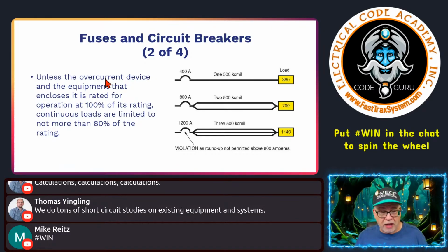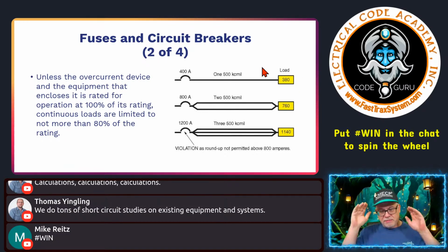But if we're following the next size up rule and everything applies, then this is an example. But what you'll notice is that this conductor of 500 kcmil copper, always assume copper unless stated otherwise, is only good for a certain amps. So since an overcurrent device doesn't correspond, it can be terminated on a 400. Well, as long as the conductor is sized to handle the load, no harm, no foul.